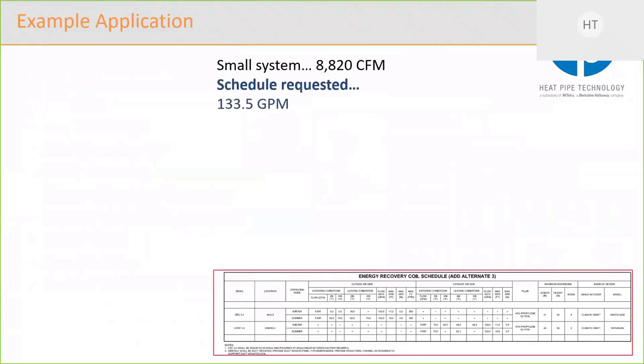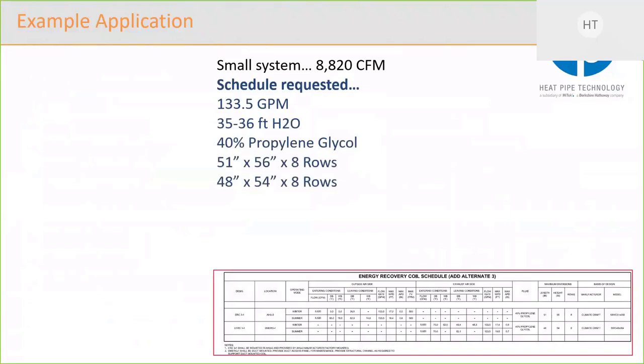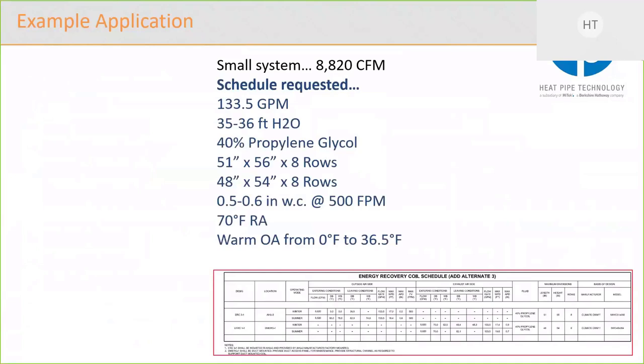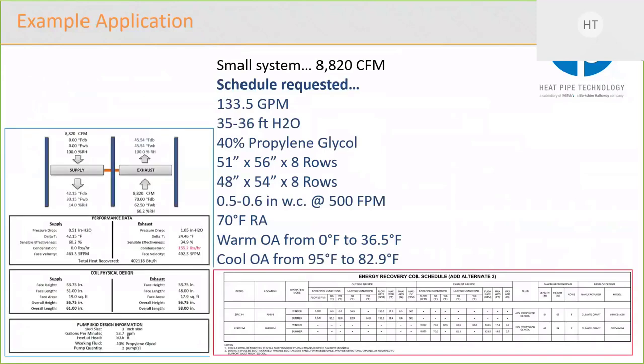So the schedule requested a system that had 133 gallons per minute. The accumulated head drop through the system was 35 to 36 feet. It required 40% propylene glycol, and it had two different size coils, one in supply, one in exhaust. They were similar, but a little bit different to each other. The pressure drop across those coils was a half inch to 0.6 inch at 500 feet per minute. The return air was 70 degrees, and when we were warming the outside air in winter, the schedule was requiring us to warm it from 0 up to 36.5. In the summer, it was requiring us to cool from 95 down to 82.9.